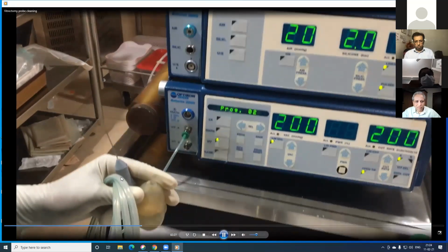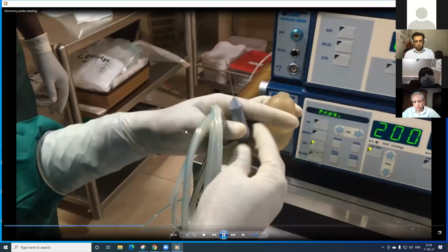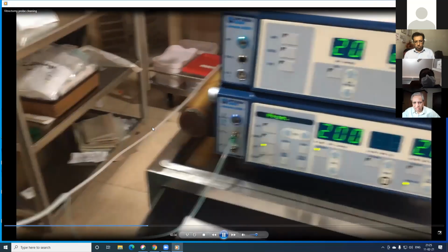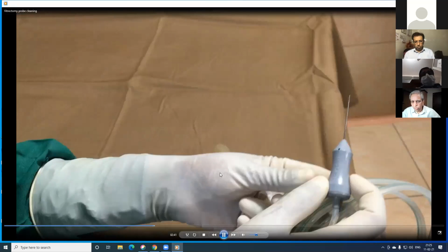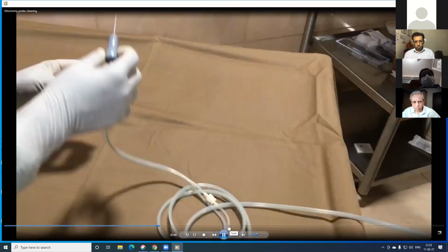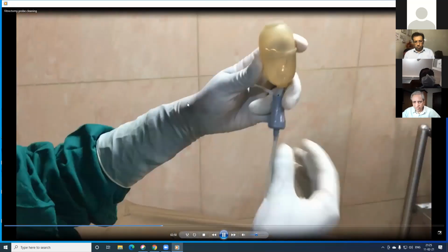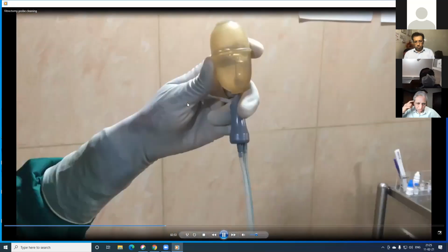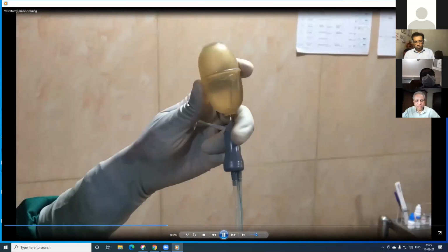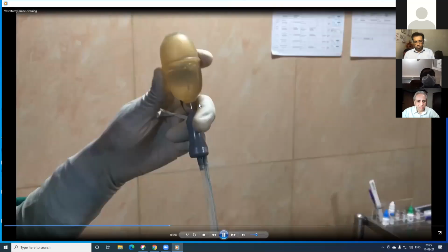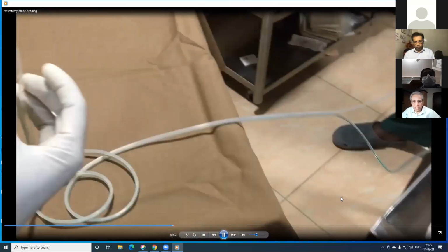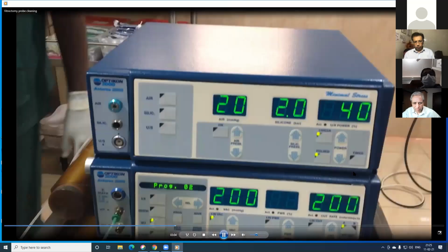So the fluid has to fill the tube before you put it to the eye. She has the bulb in her hand, which is filled with BSS. This is all unsterile, actually. Don't mistake it that there's a surgery going on. So she compresses the foot switch and dips it in the fluid and sees that the entire pipe is filled with water. This is very important. Otherwise, suddenly the vacuoles of air can create unnecessary excess or low pressure. So this is filled with fluid before she hands it over. That also tests whether the cutter and tube are working.